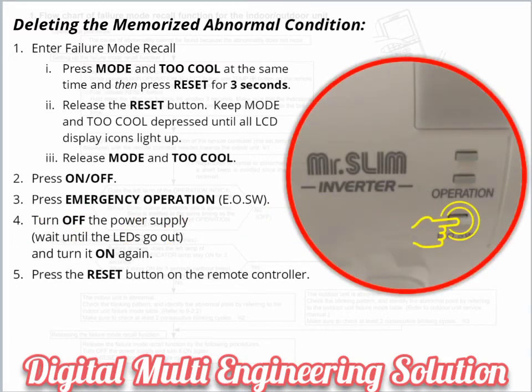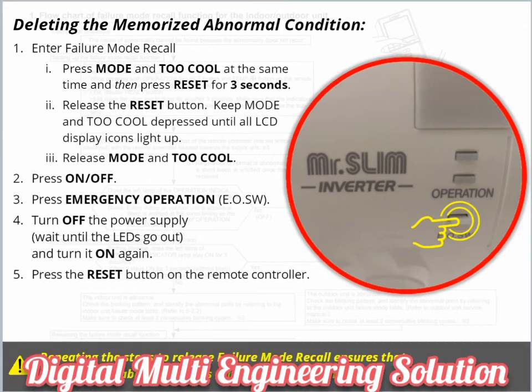Next, press the emergency operation switch on the indoor unit. Return to the power supply and turn off the unit. Wait until the LEDs go out and turn it back on again. Finally, press Reset on the remote controller. Repeating the steps to release Failure Mode Recall ensures that no additional abnormal codes remain in the system.